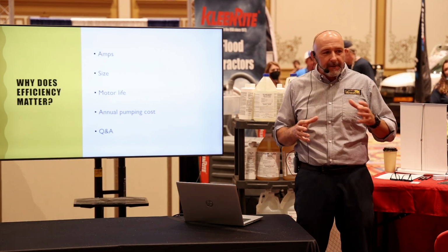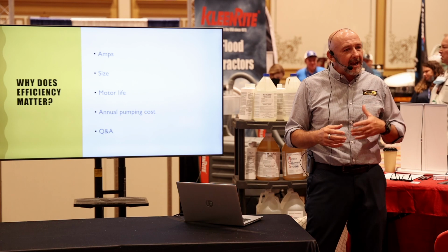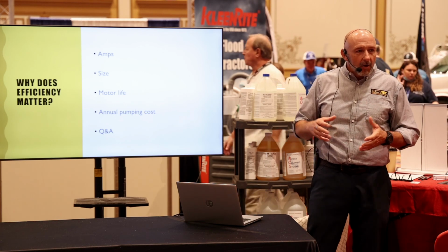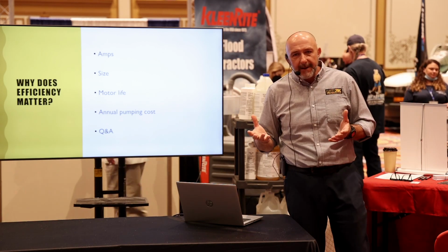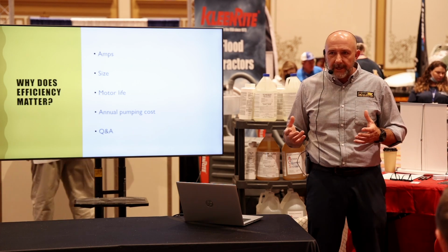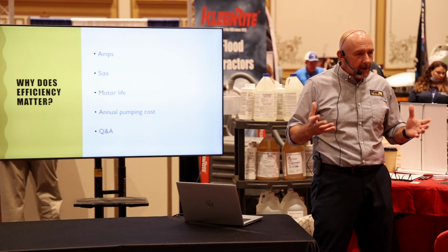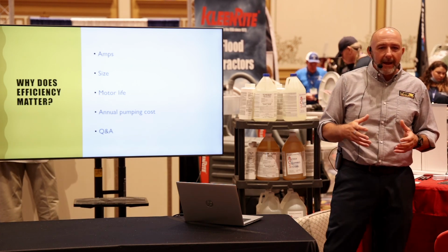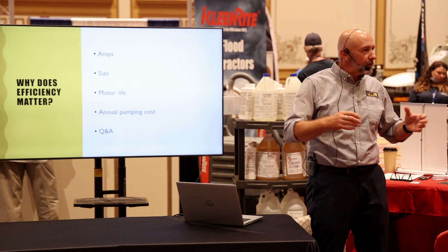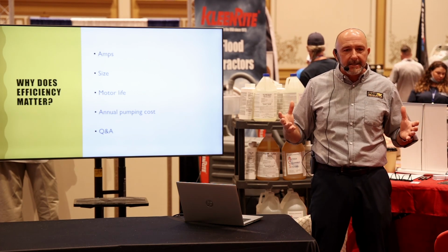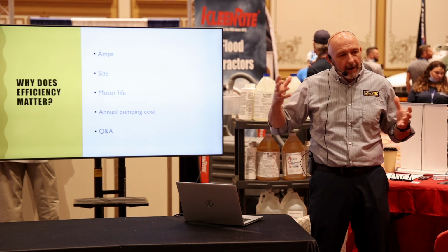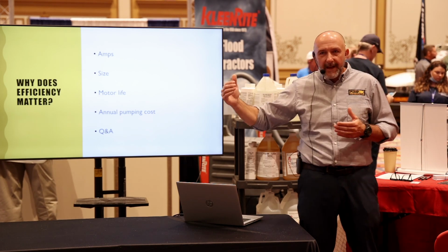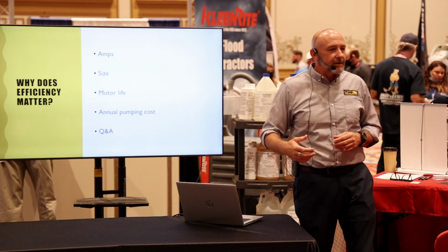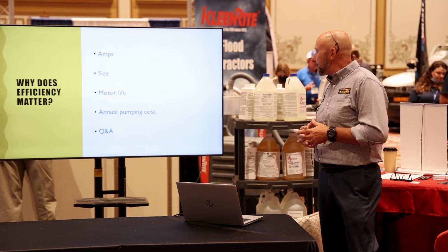Because we don't have any inefficiencies in our design or in our motor speed, we don't have any additional amp draw. And that amp draw is extremely important for what we do because we're limited to a 15 amp breaker on these portable extractors. And we have a lot of other components and vacuums and heaters that we need to utilize in this system that require higher amps. And if we go over that amp draw, you're blowing breakers in the field. It's creating problems for you that you don't need.